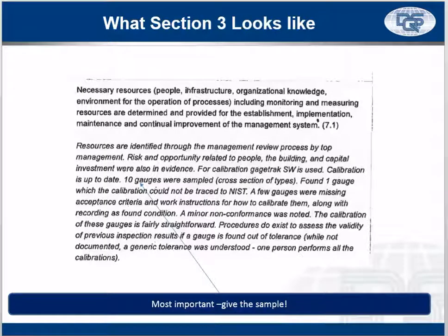What does your section 3 look like? Okay, so the important part of all this, and this is section 3 from a different report, not related to the notes, the important part of all this is the sample. This is what you want to have noted here. How many did you sample? And you can make some statements if you want about whether it could be traced. Here was 1 gauge that could not be traced, so there was an AR associated with this. Some were missing acceptance criteria, so a minor nonconformance was noted. Okay, so it's pretty straightforward how to document calibration. And again, the important thing is the sample size.